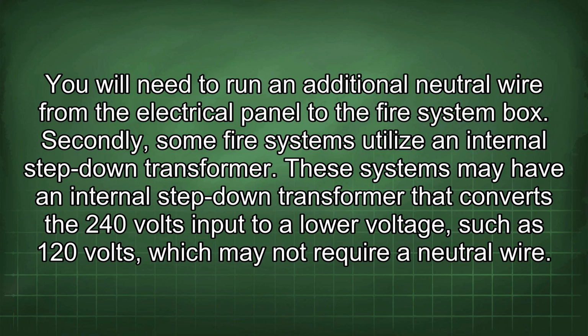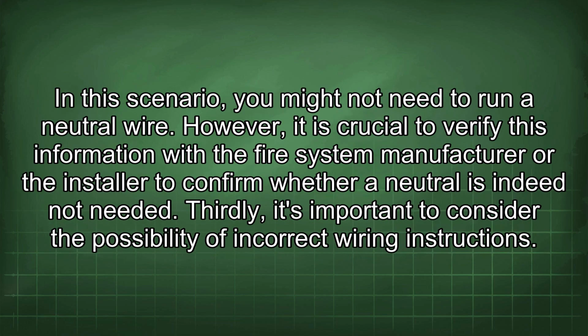Secondly, some fire systems utilize an internal step-down transformer. These systems may have an internal step-down transformer that converts the 240 volts input to a low voltage such as 120 volts, which may not require a neutral wire. In this scenario, you might not need to run a neutral wire. However, it is crucial to verify this information with the fire system manufacturer or the installer to confirm whether a neutral is indeed not needed.